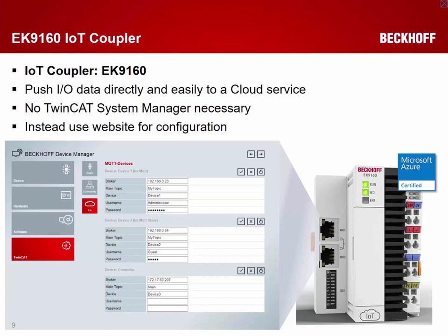From the handling, it's very similar to a Fritzbox, right? Like a DSL router, where you also have a website on the device. You just open the website from your laptop, from your desktop PC, and then you can configure the device. And what you can configure on the EK9160 is, of course, the message brokers that you want this device to communicate with.